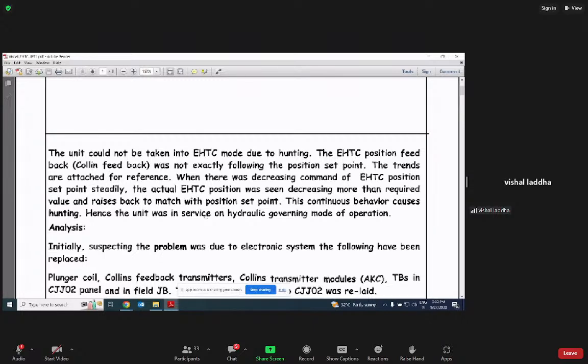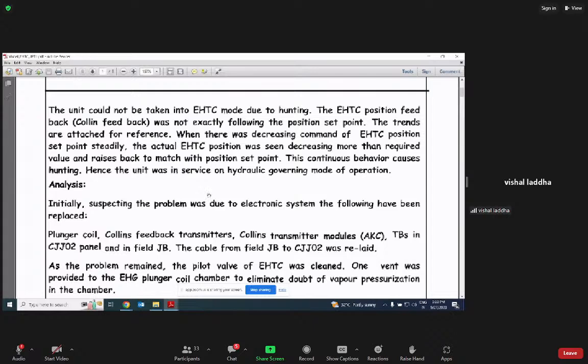rectify the problem. When the EHTC position set point command was decreasing steadily, the actual EHTC position was seen decreasing more than the required value and then rising back, meaning the command and feedback are continuously oscillating to follow each other. Command is following feedback and feedback is following command. This continuous behavior caused hunting as the unit was in service only in hydraulic governing mode operation.